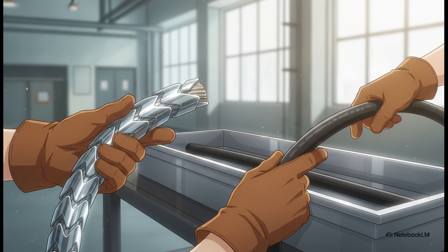In industrial establishments that are inaccessible to the public, you can use Type TC or TCER tray cable. You can also use single insulated conductors like R90 or RW90. But here's the catch with that. They cannot be smaller than 10 AWG. You're not going to be running little number 12 single wires loose in a tray. They have to be heavy-duty, 10 AWG or larger.